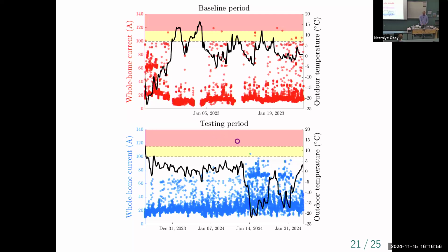And this is the testing period, same graph. And again, the black is the outdoor temperature. You can see that we got lucky basically and caught a super cold snap. I'm probably the only person in Indiana who was praying for the coldest possible day in the middle of January, but we got one. And so we got good data there as well. And you can see that almost always we robustly maintain the current below 100 amps, although there was this one 5-minute period where we went slightly above.